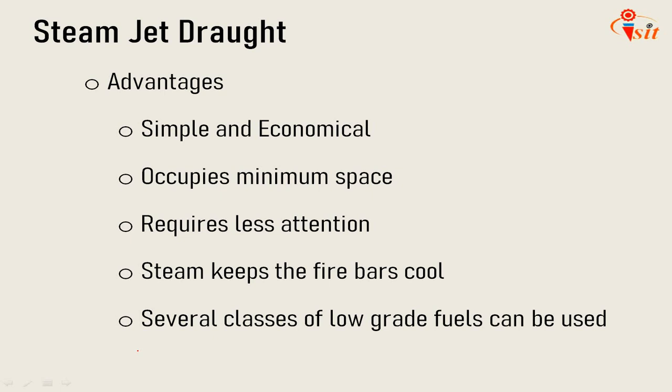There are certain advantages of steam jet draught. It is very simple and economical, occupies minimum space, and requires less attention. In forced type steam jet, the steam keeps the fire bars cool and prevents the adhering of clinker to the fire bars. Several classes of low grade fuels can be used within the system. Okay, so these are the advantages of steam jet draught.